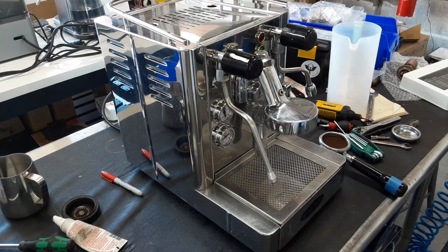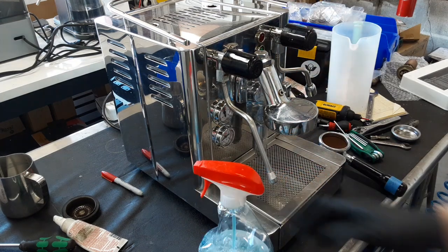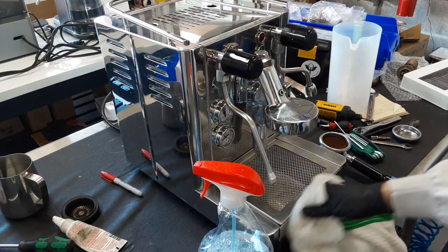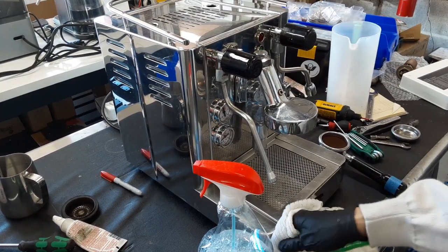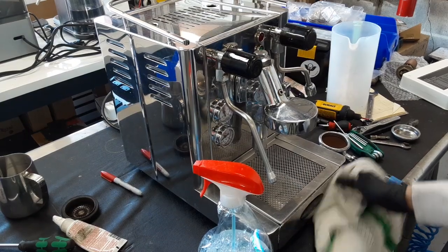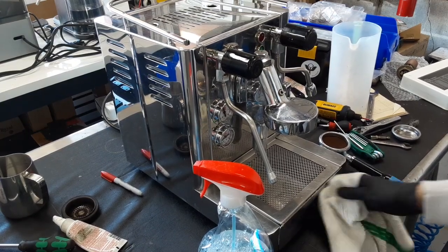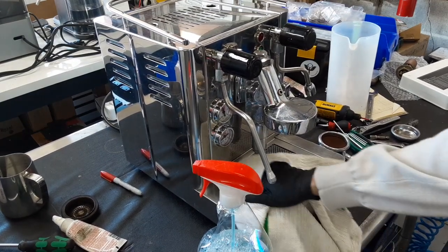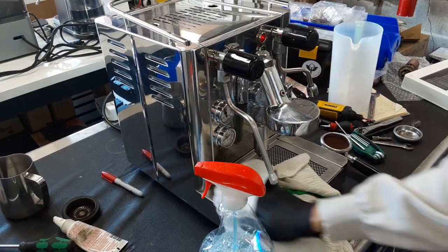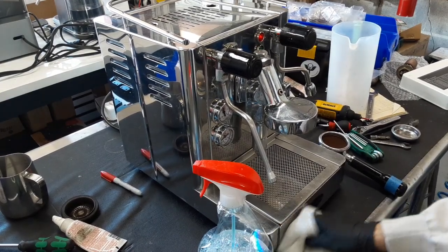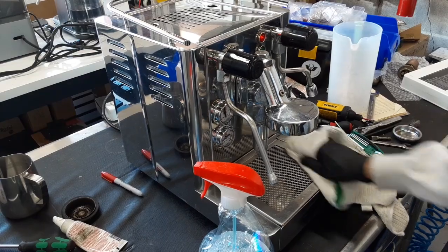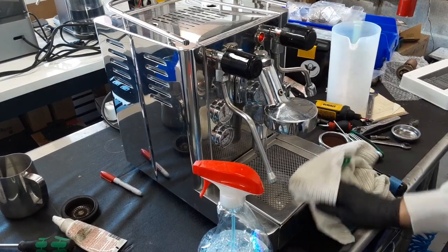Starting off, the machine was completely clogged, and we had recently replaced the pump last year. Going inside, I saw the pump was still from 2022, so it was a very recent pump change, and it was just completely clogged. I kept doing some research afterward, troubleshooting to see what was clogging it, because a new pump shouldn't have died out after a year.